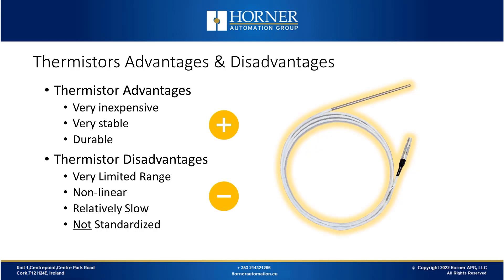The advantages of thermistors are that they're very stable, inexpensive, and durable. Some disadvantages are that they have a very limited range, are non-linear, relatively slow, and not very well standardized. Thermistors on the surface could appear similar, but if purchased from two different manufacturers they could behave quite differently because they have different temperature curves.